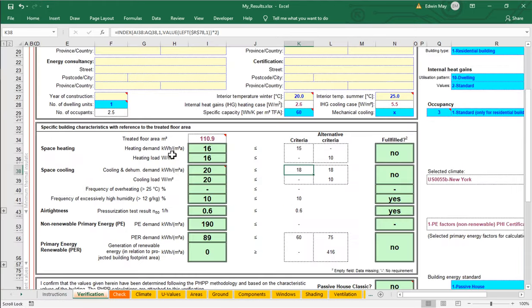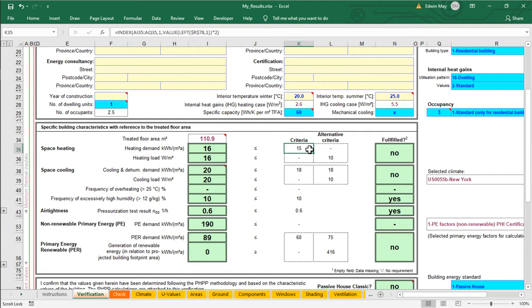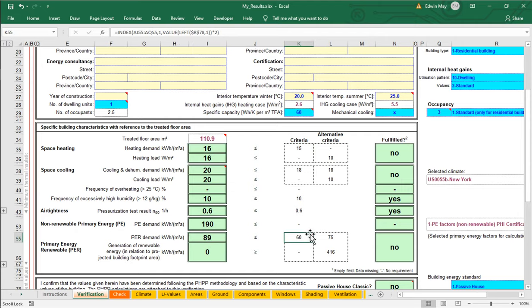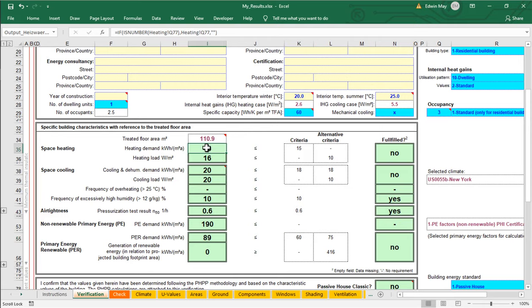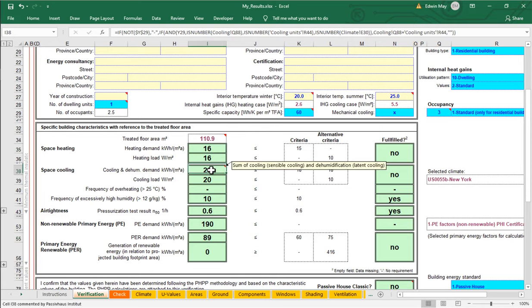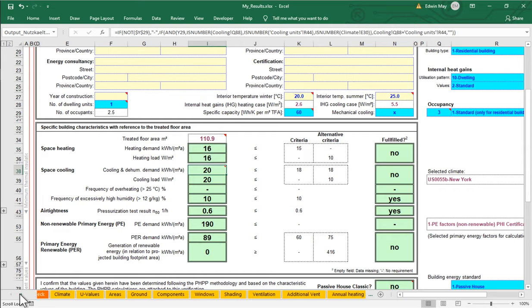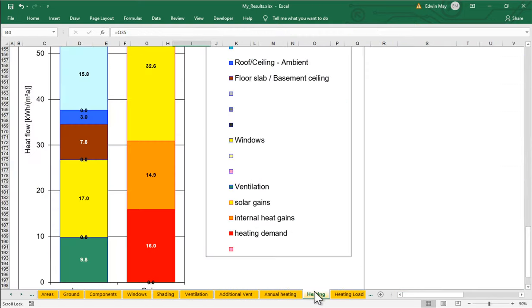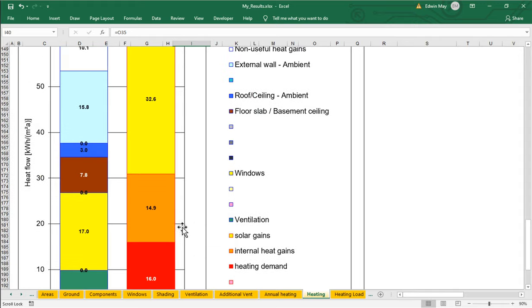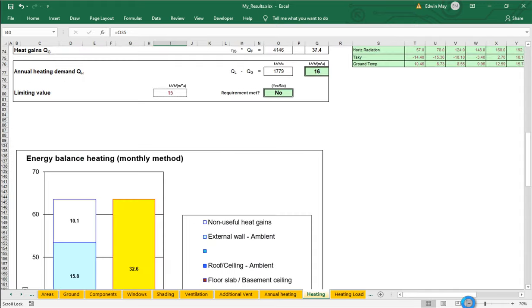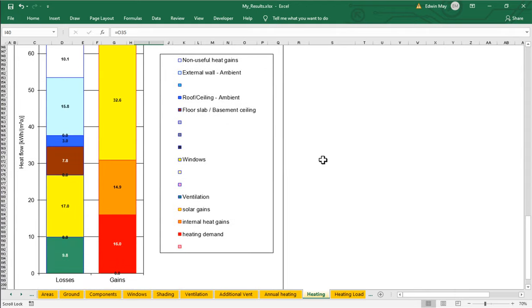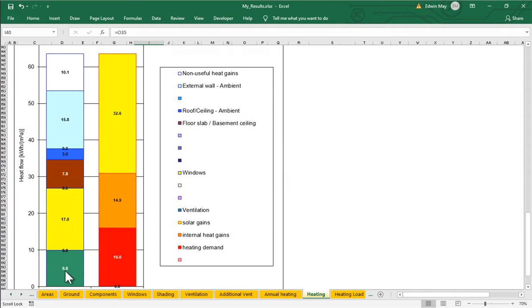We're at 16. We've got to get to 15. We're at 20. We've got to get to 18. I'm at 89. We've got to get to 60. So what else can we do to this project to improve performance? Well, the other thing that we might do, we're still over on heating, we're over on cooling, we're over on primary energy. Let's go back and take a look at our annual heating energy demand worksheet.